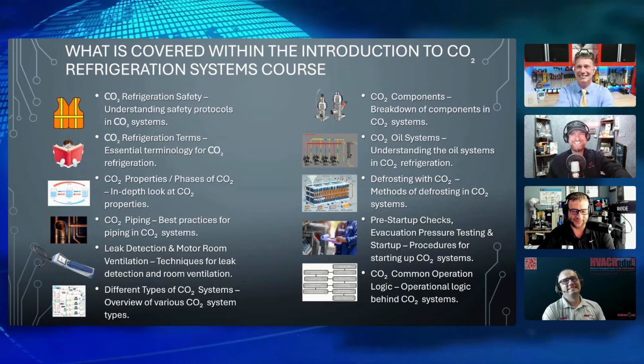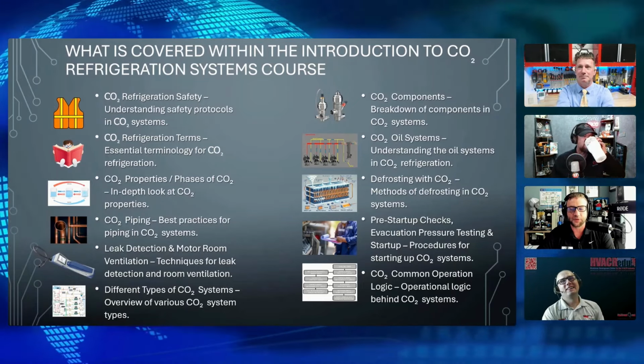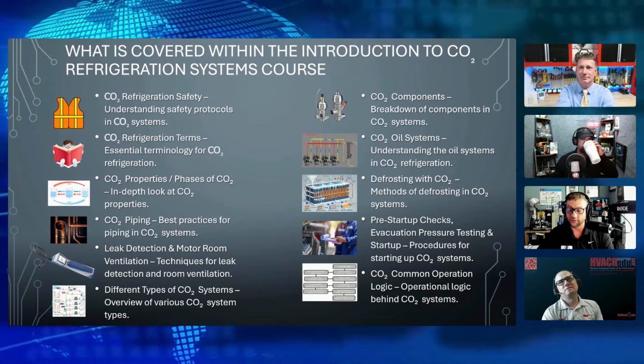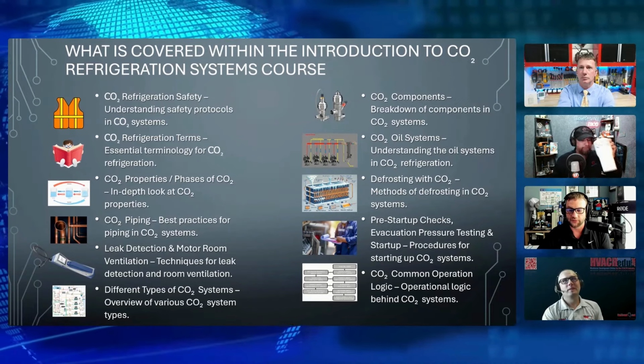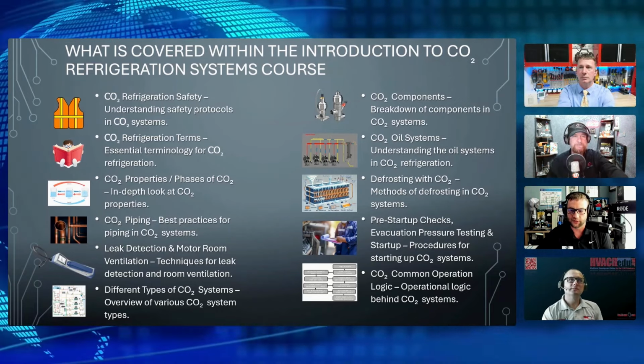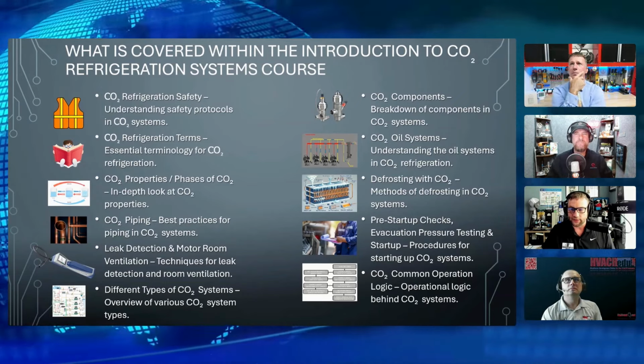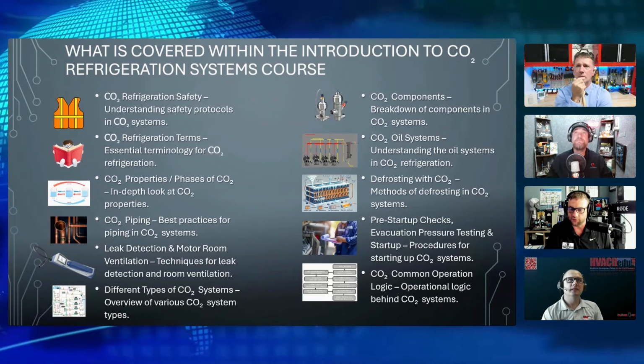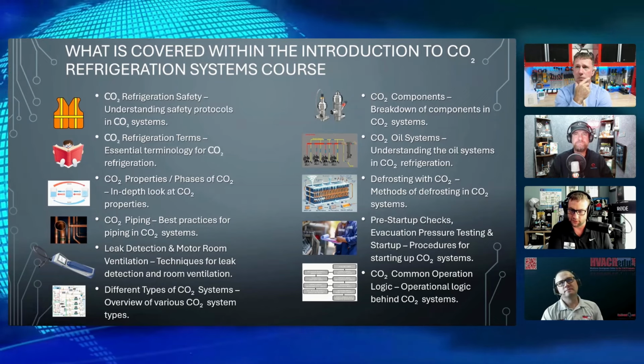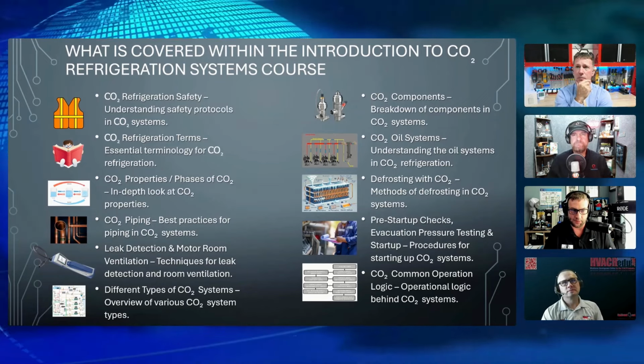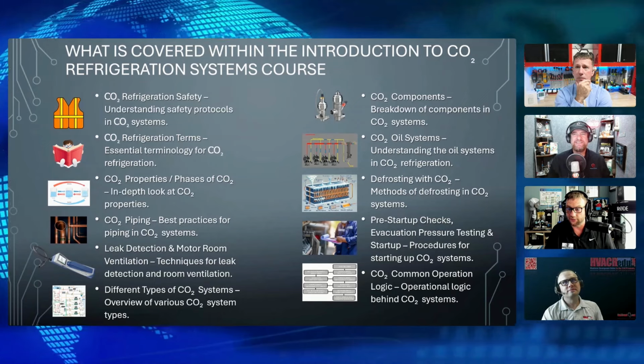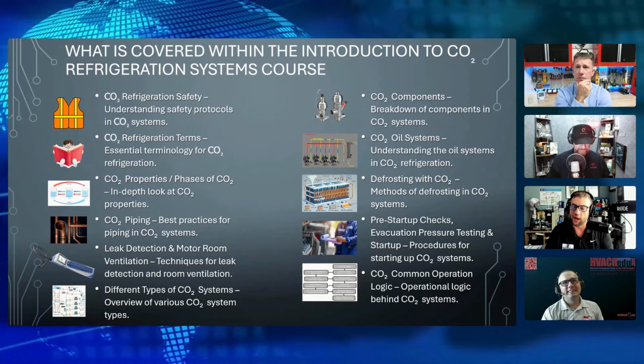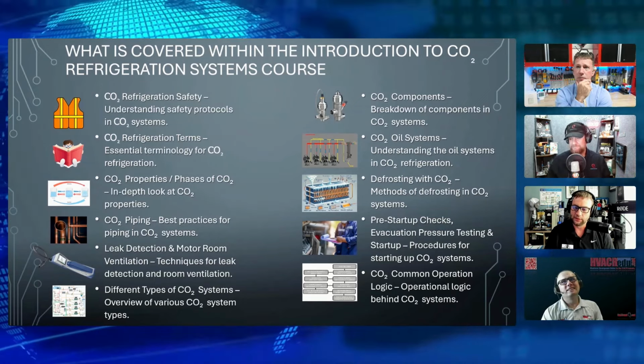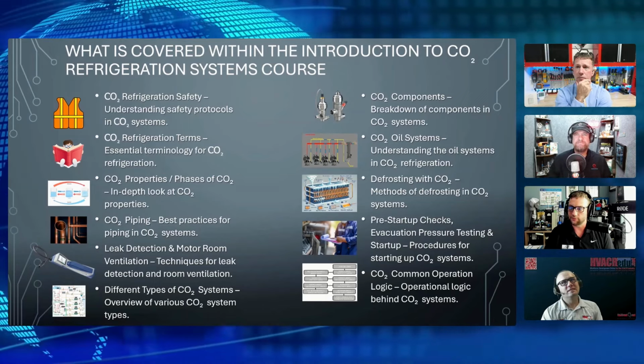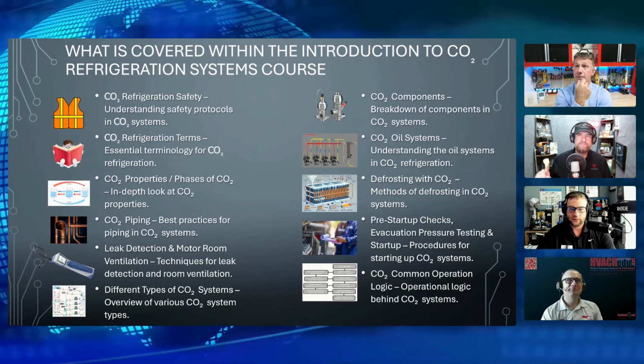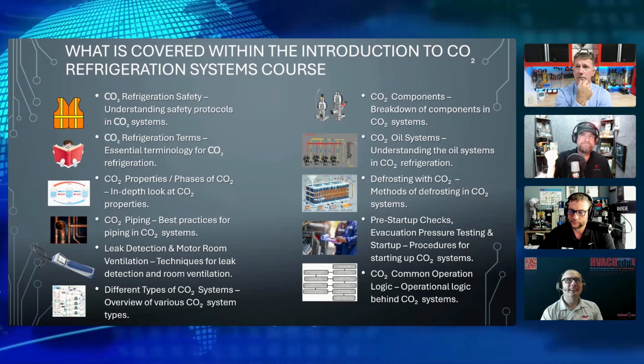But I was going to say that there are leaks, but not the purple and white ones. Basically, you have rotting vegetables, and rotting vegetables give off CO2. So I'm telling you some of these things that could potentially trigger a detector. Rising bread, too. I've had service calls where a leak detector went off in one of these walk-in coolers, and I'm like, oh, well, there's no leak. Why is there no leak? Because there's not really a leak. I timed it and talked to the bakery lady, and she said, oh yeah, we put the rising bread in there around 7 o'clock, and that's when the alarm went off. That is very, very important information when we start talking about refrigerant leak detection.